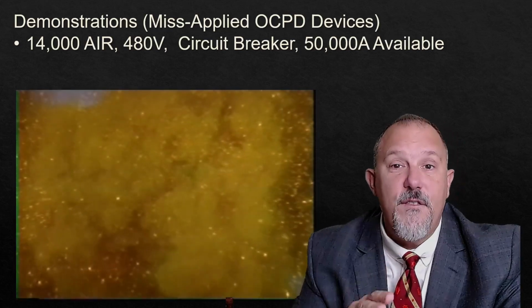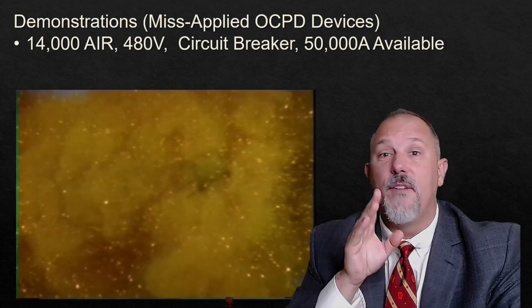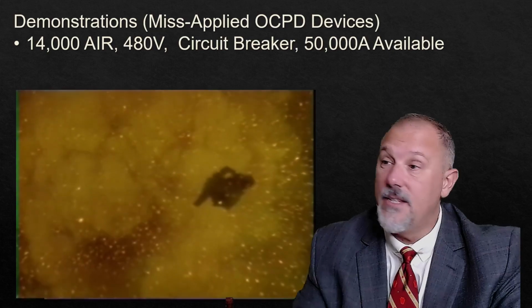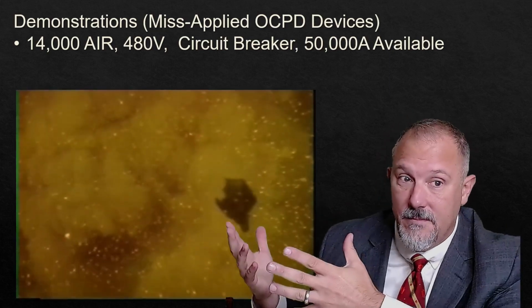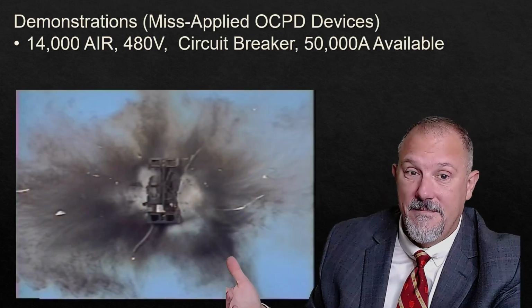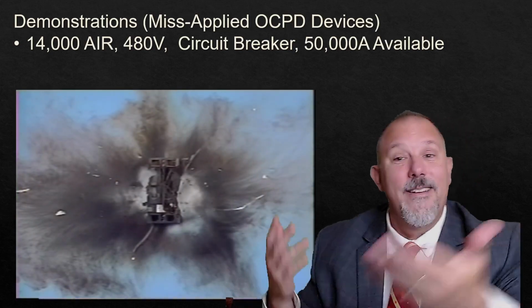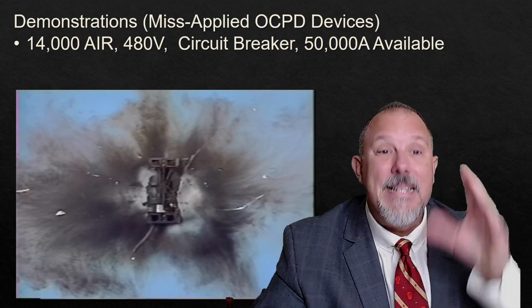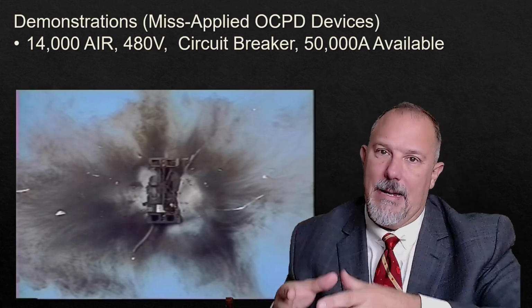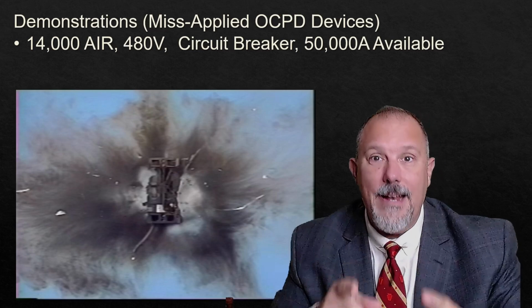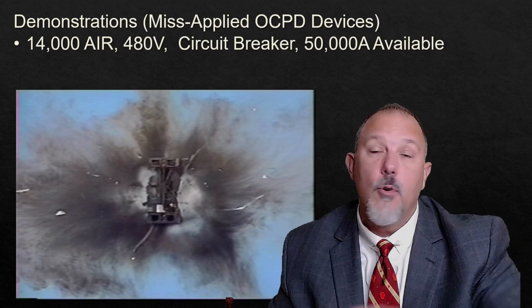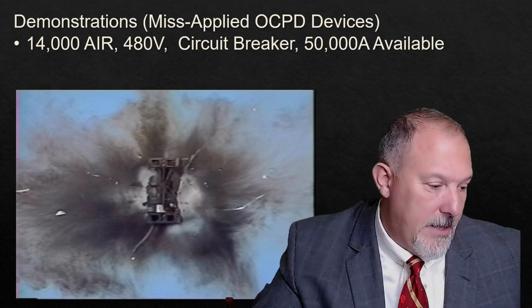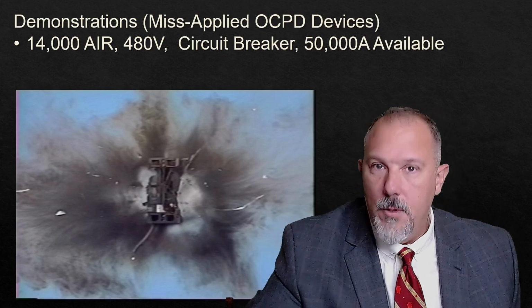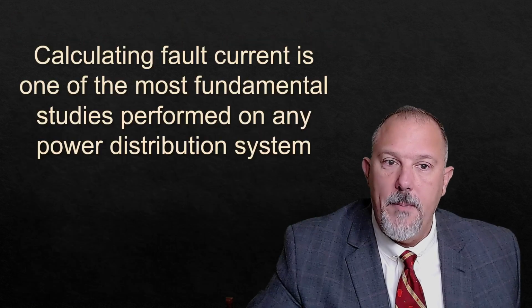The interrupting rating is only 14,000 amps. With 50,000 amps, it tried to stop the flow of 50,000 amps. Again, this is a serious misapplication. That's right. So when you misapply a product in the field, you could get an unintended rapid disassembly in the field. It would be bad.